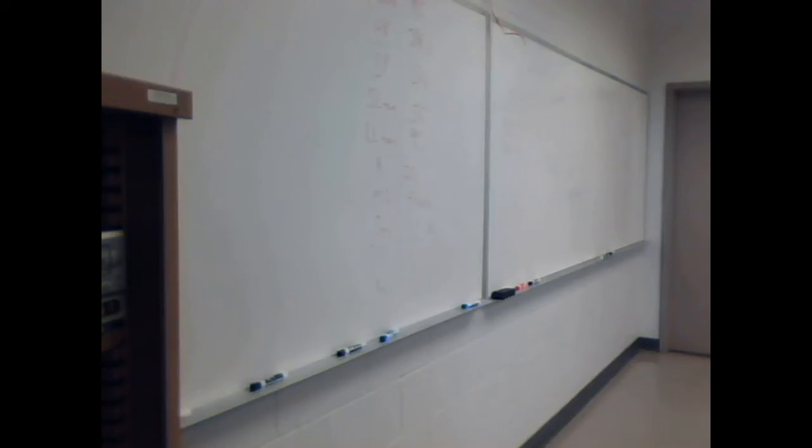So what does it line up with, y'all? Does it line up with anything, or 2 or 3? Liquid restriction. What is a liquid restriction? Probably a filter dryer, right? How are you going to test that in the real field? If I give you a liquid restriction, take the temperature across it. If there's a pressure drop, there's probably going to be a temperature drop. Also, you could have a TXV feeler bulb charge. The reason you eliminated that was because we don't have a TXV. That's exactly right.